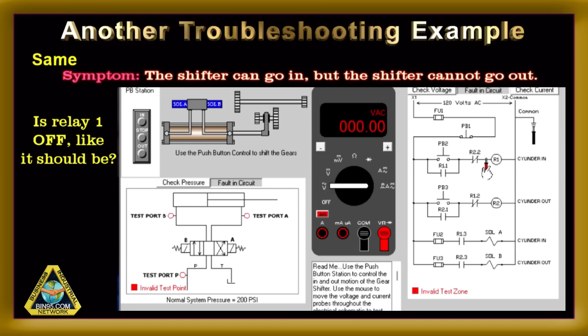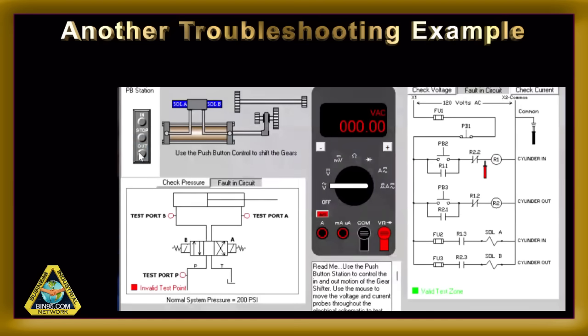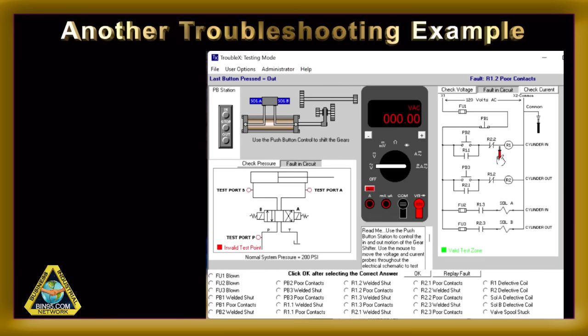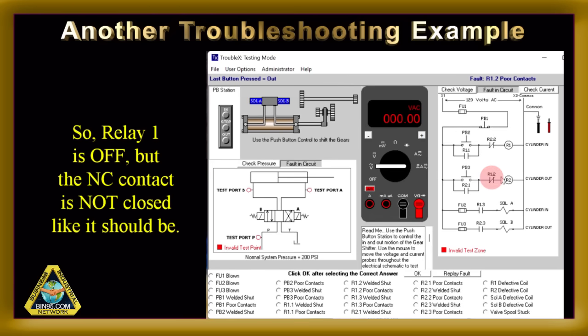Voltage on the left side of a contact and not on the right side indicates the contact is open. So, check R1 coil — it should be off, 0 volts. The fault is that R1 is off but the normally closed contact is open. To repair, you would replace R1 or its bad contact. In the TroubleX simulation software, the learner would select R1.2 poor contact as the correct answer.